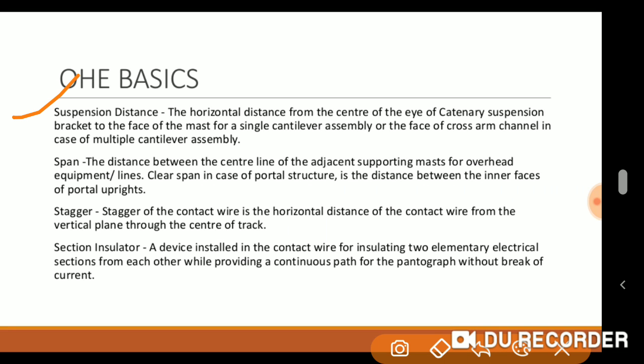Suspension distance: the horizontal distance from the center of the eye of catenary suspension bracket to the face of the mast for a single cantilever assembly, or the face of cross arm channel in case of multiple cantilever assembly. Span: the distance between the center line of the adjacent supporting masts for overhead equipment lines. Clear span in case of portal structure is the distance between the inner face of portal uprights. Stagger of the contact wire is the horizontal distance of the contact wire from the vertical plane through the center of track.